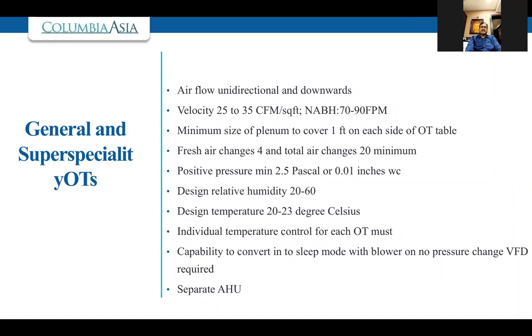Fresh air changes. This is a change from the previous guidelines. Positive pressure, again, the limits have been brought down. Design humidity levels also we have brought down, up to 20 percent. There's no harm in having 20 percent minimum also. Design temperature has been rationalized in these guidelines. Individual temperature control has been made compulsory in each OT, temperature as well as humidity. So there has to be a sensor or monitor placed in each OT.